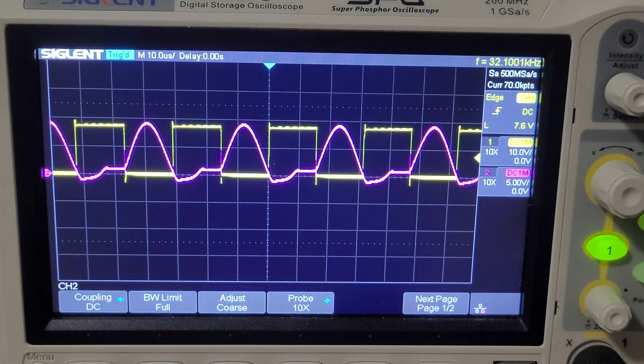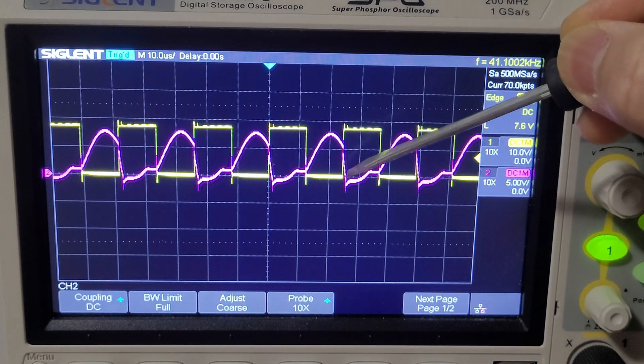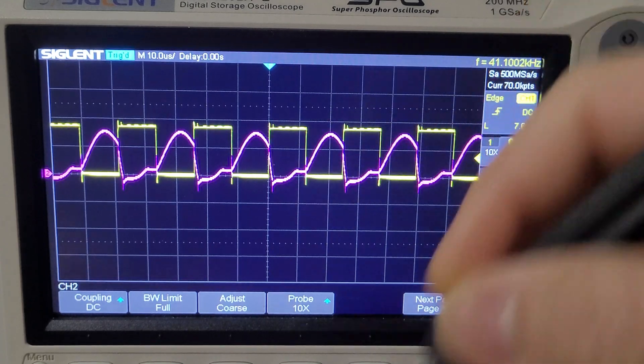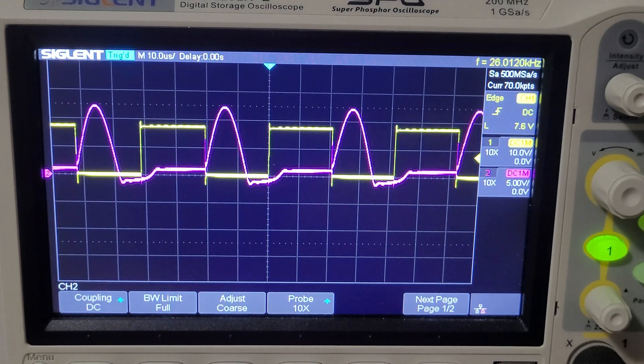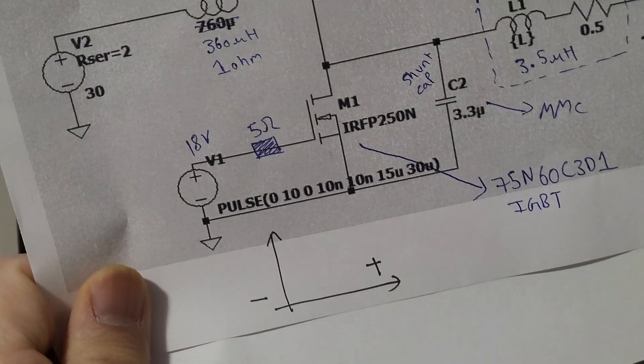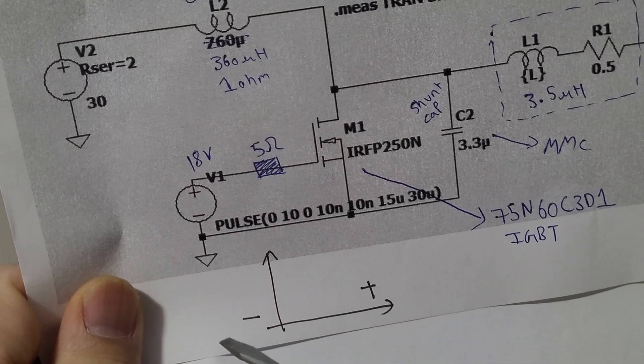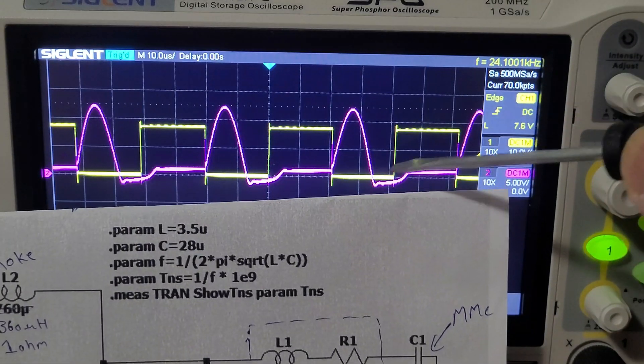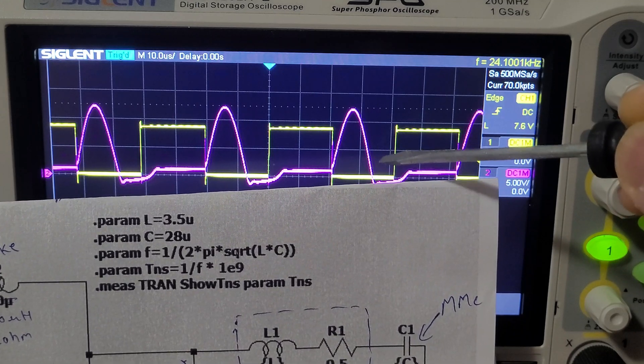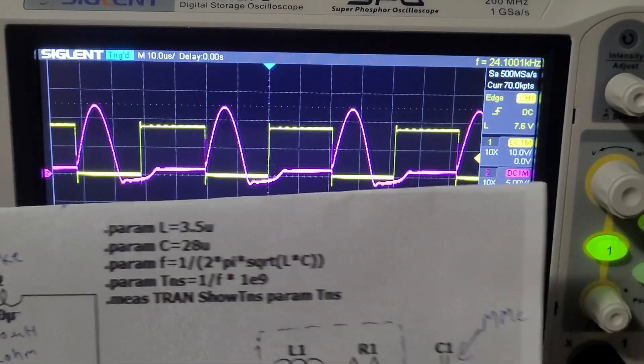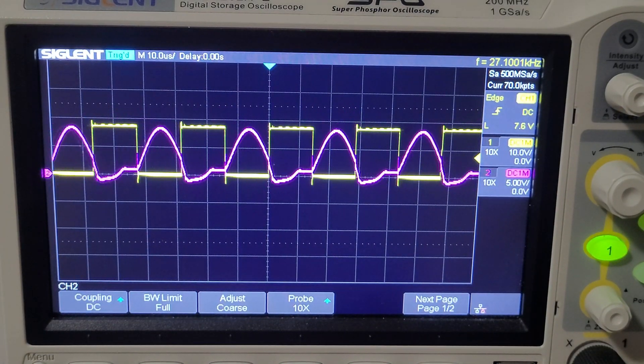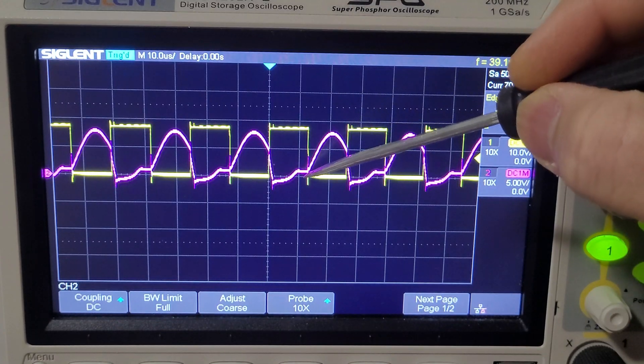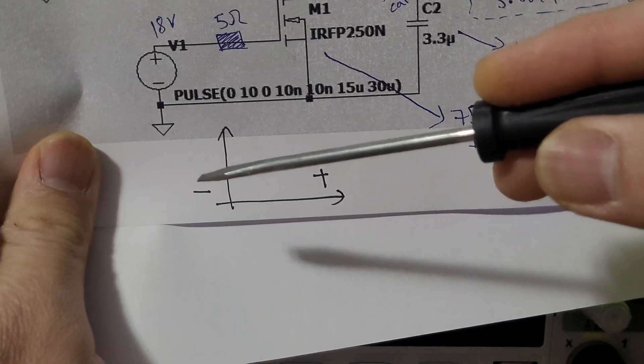If your waveform looks flat here, then your frequency is too high. If it looks like this, then your frequency is too low. I'll show you an easy way to remember it. Like in school when we made graphs, this side was negative and this side was positive. If your waveform looks like this with space here, just increase the frequency. If there's space on the other side or it's flat out here, just decrease the frequency.